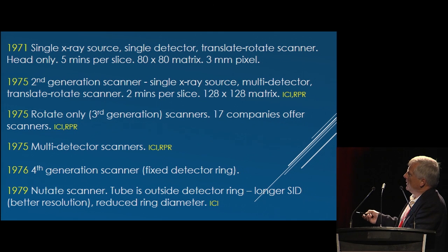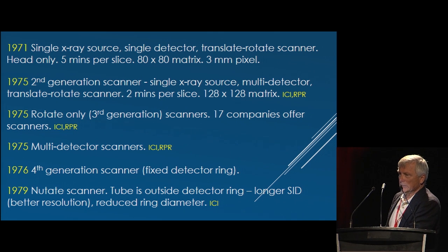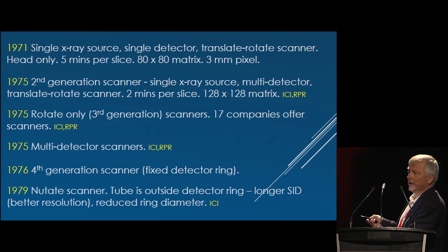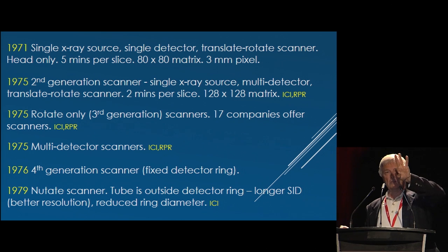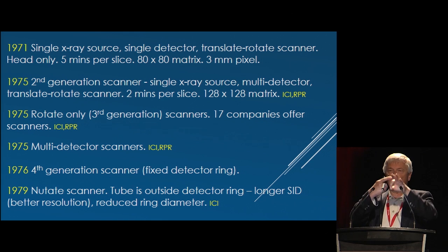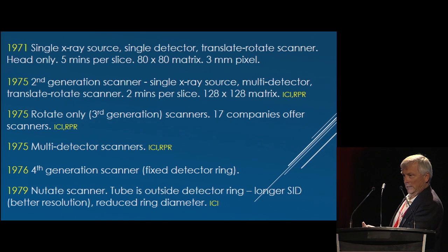In 1979, there was the introduction of a nutate scanner. This is where the X-ray tube was in fact outside the detector ring, and so the detector just sort of wobbled like this as the X-ray tube moved around it. Why did we have that? Well, it provided a longer source to image distance, which gave better resolution, and it reduced the ring diameter, which was an improvement in clinical information.